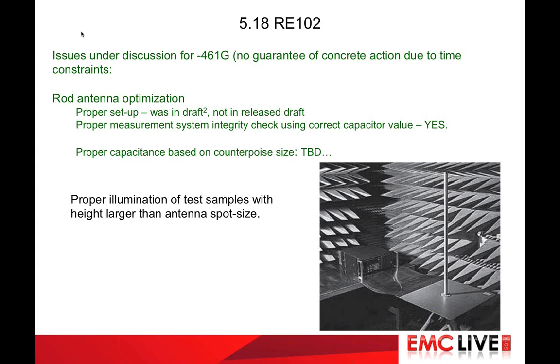Two methods of obtaining isolation are transformer and optical. Transformer is a pretty cheap modification, but to date there are issues with transformer performance. Optical works, but is expensive. Second issue, typical rod antenna whips in the past have been quite thin, and the old standard assumed value of 10 picofarads was a useful approximation. There are rod antennas on the market now with rod diameters approaching a centimeter. For these, 15 picofarads comes closer. The standard takes cognizance of this by stating that the manufacturer's suggested value should be used.